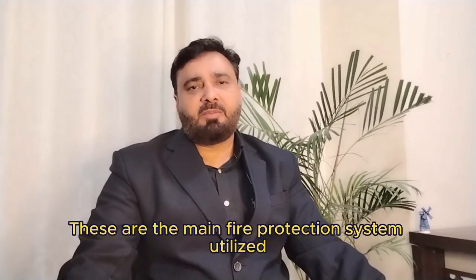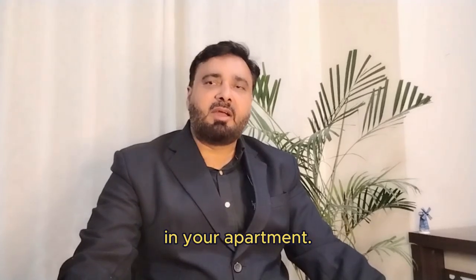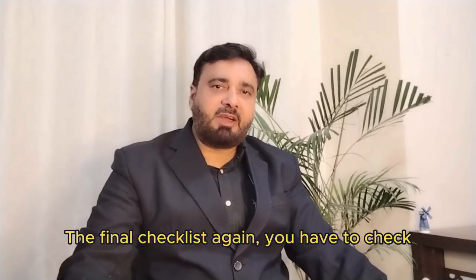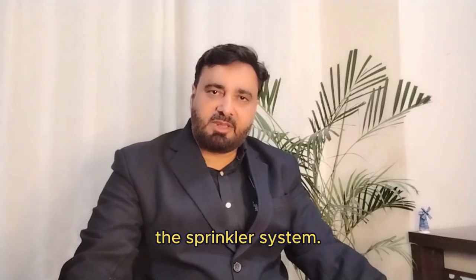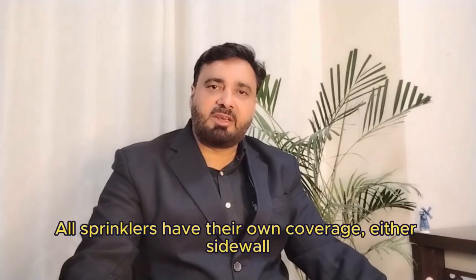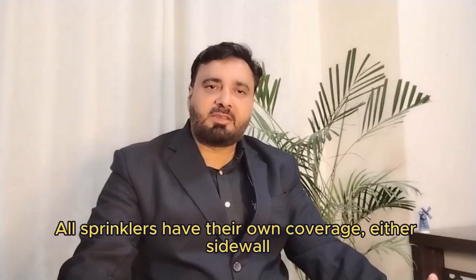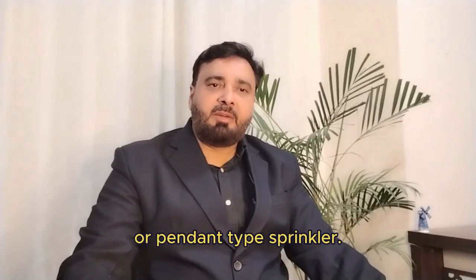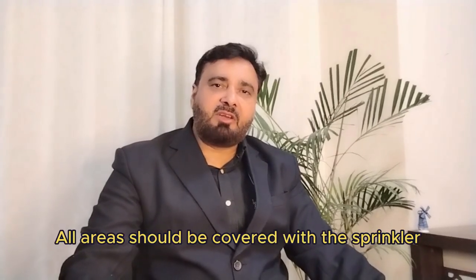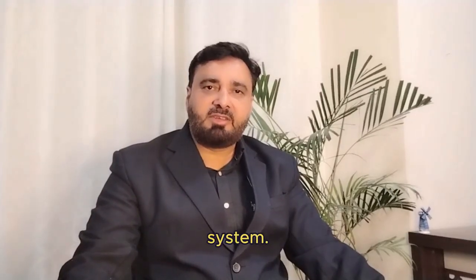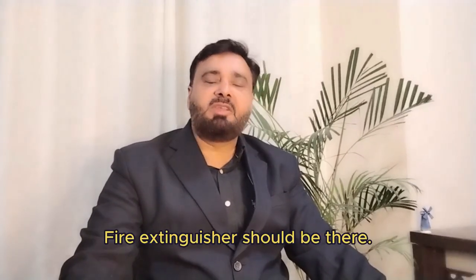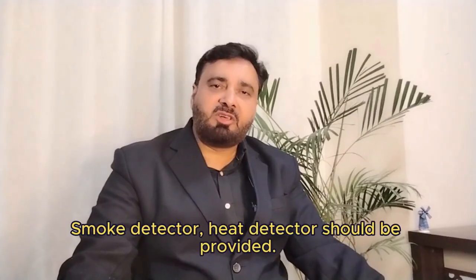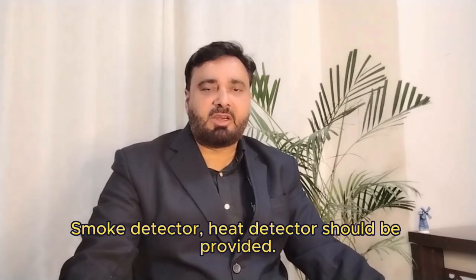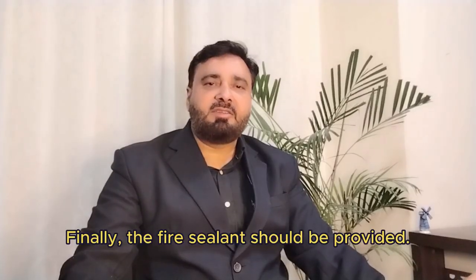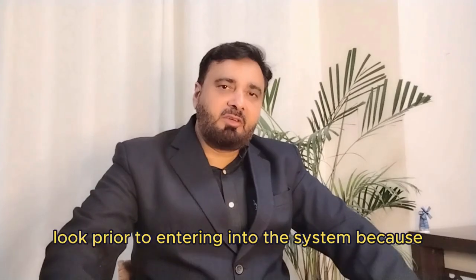These are the main fire protection systems utilized in your apartment. In the final checklist, again, you have to check the sprinkler system. It is there. All sprinklers have their own coverage, either side wall or pendant type, and the whole area should be covered by the sprinkler system. Fire extinguisher should be there. Fire blanket should be there. Smoke detector and heat detector should be provided. And finally, the fire sealant should be provided. These are the main things you have to look for.